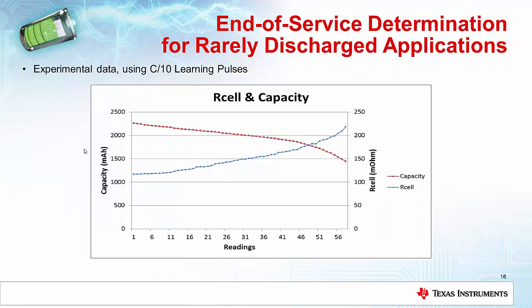You can see some examples of data that we've taken, where we started out with around 2300 milliamp hour capacity, and then over time it degraded with multiple cycles down to a little under 1500, so about a 35% reduction. You can see the effective cell resistance that we measured using this algorithm, where it started out on the order of 115 milliohms, and as the cells degraded, it increased up to on the order of 220 milliohms. This lets us determine the health of the battery, and we have programmable thresholds in the part where we can generate alerts and warnings back to the host system, to alert them that we're nearing the end of the usable service of the battery. You should consider replacing the battery pretty soon.